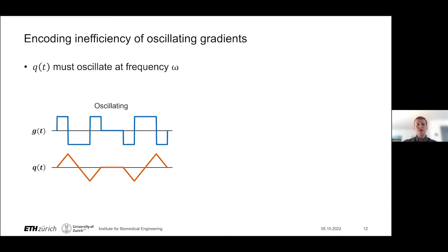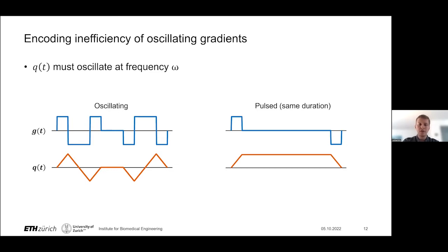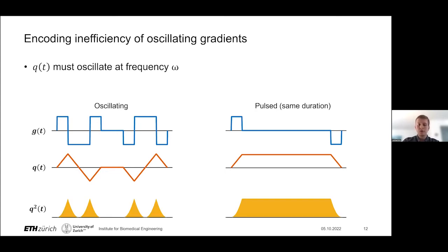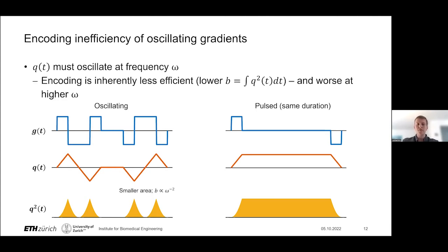One main drawback of using oscillating gradients is that they are an intrinsically inefficient form of diffusion encoding, exactly because of these oscillations. Comparing to the pulse gradient case without oscillations: on the left, q(t) oscillates about zero, while on the right, q(t) is a constant positive value in a trapezoid. Looking at q², in the pulse gradient case — no oscillations — we have a constant positive area, whereas in the oscillating gradient case we have multiple lobes and less accumulated area overall due to these oscillations. This is exactly the mechanism for encoding inefficiency, and it becomes worse at higher frequencies.